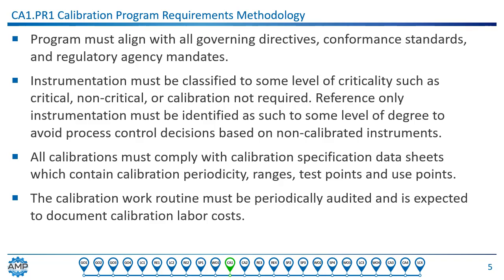Reference-only instrumentation must be identified as such to avoid process control decisions made on non-calibrated instruments. All calibrations must comply with calibration specification data sheets, which contain calibration frequency or interval, ranges, test points, and use points. Beyond providing correct and consistent calibration instructions for the technician, these data sheets are very important toward proving calibration and timeline in the event of a deviation investigation. This supports audit trails during periodic audits as well as investigation for corrective actions. The calibration work routine must be periodically audited and is expected to document calibration labor cost, and continuous improvement should be a goal of any calibration program.